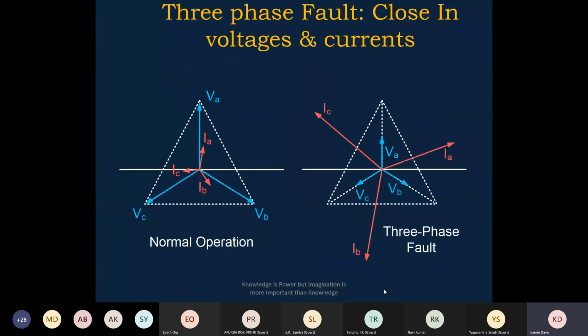Okay, now if you look at it here, on the left side, it is the load condition, the vector, where VA, VB, VC: VA is 63 volt, VB is 63, VC is 63, IA is 1 ampere, IB is 1 ampere, IC is 1 ampere, and 10-20 degrees lagging. You look at it here. So normally this is called the normal load condition or normal operation. When there is a fault, you look at it here. VA is reduced from 63 to 30 volt. VA, VB, VC have reduced. IA, IB and IC have become higher.